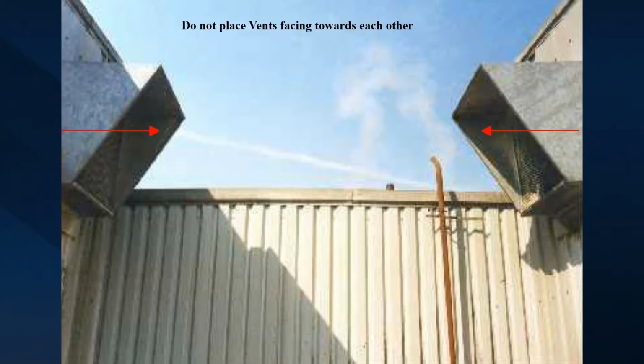Do not have vents opposite to each other. If you have an explosion in this volume here, it will open this vent to the inside, and then you have an explosion in the second. In this case, it was 2 baghouses. So the explosion here goes into this baghouse, and from the baghouse then, because of non-existent explosion isolation, into all connected equipment that you had there. And that is not so good to have.